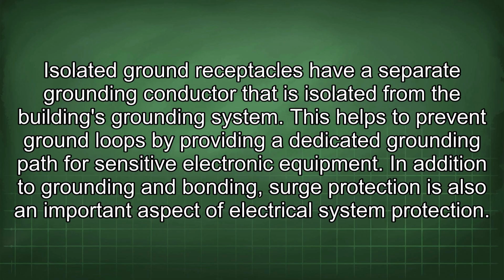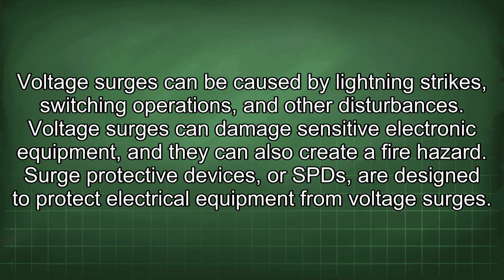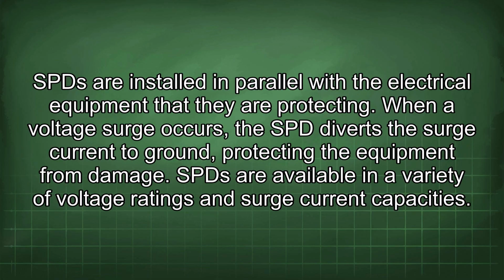In addition to grounding and bonding, surge protection is also an important aspect of electrical system protection. Voltage surges can be caused by lightning strikes, switching operations, and other disturbances. Voltage surges can damage sensitive electronic equipment, and they can also create a fire hazard. Surge protective devices, or SPDs, are designed to protect electrical equipment from voltage surges. SPDs are installed in parallel with the electrical equipment that they are protecting. When a voltage surge occurs, the SPD diverts the surge current to ground, protecting the equipment from damage.